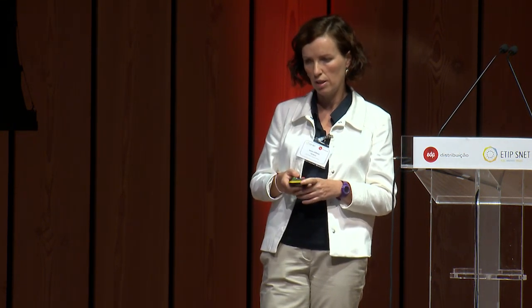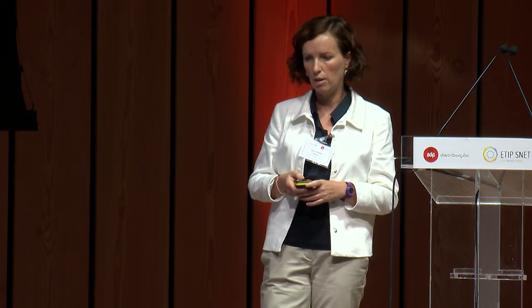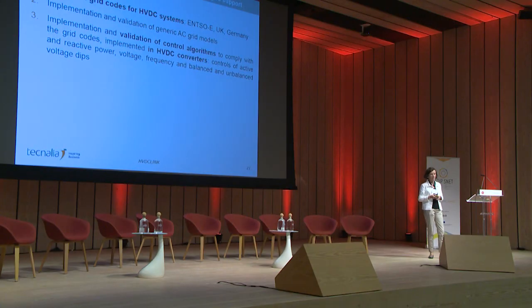We have also been working on the development of AC grid models. We selected the CIGRE test grid, as this is a mixed grid, and we have been working on phenomena such as voltage and frequency variation, balanced and unbalanced voltage ride-through, subsynchronous oscillation, and harmonic distortion. So now we have finished this analysis of grid codes and the implementation and validation of the AC grid models.